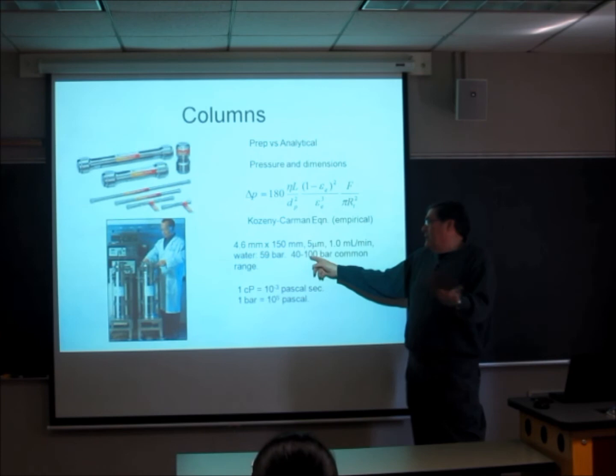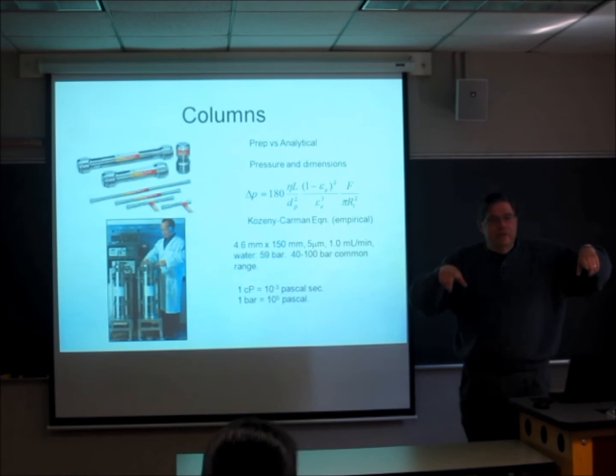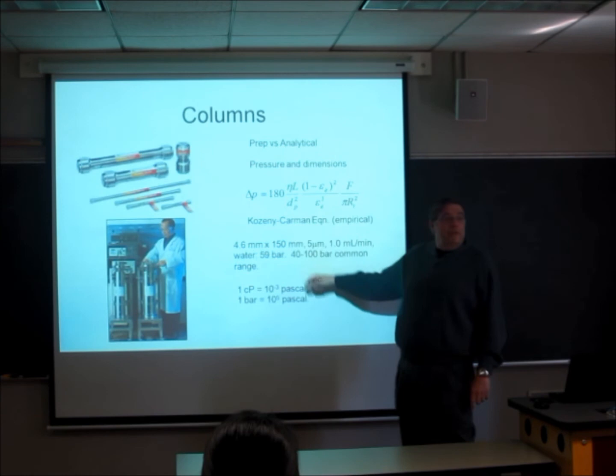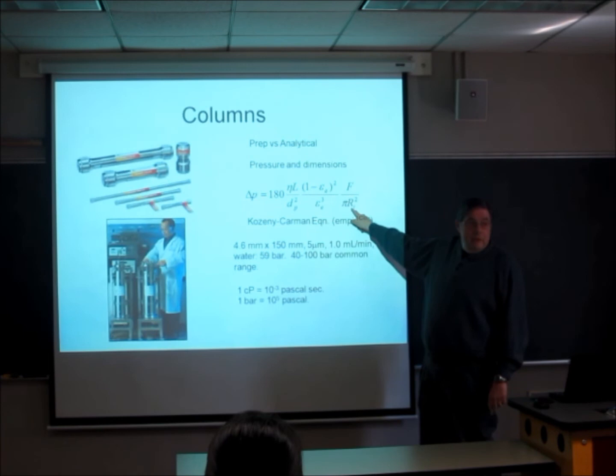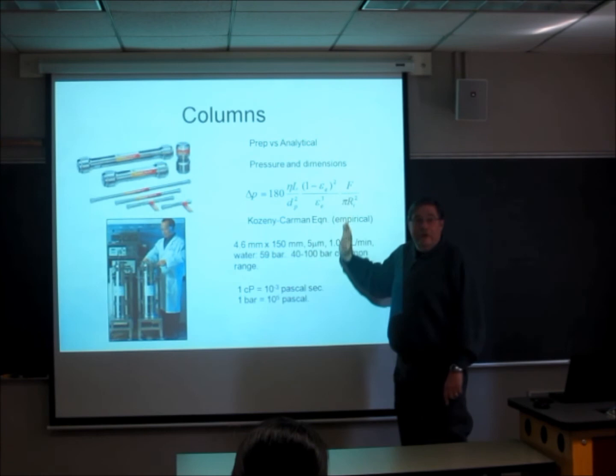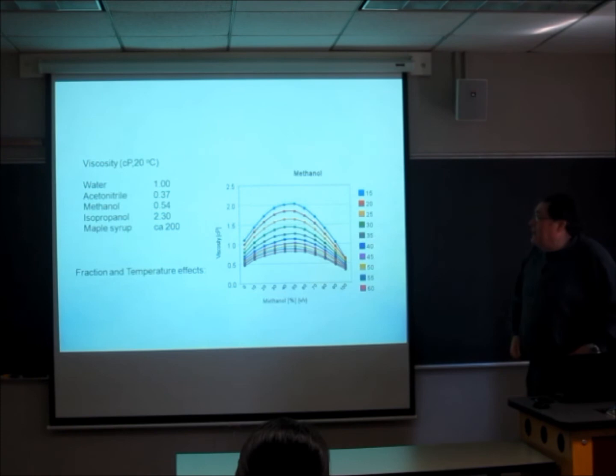There's been a lot of changes in particle diameter over the last 20 years or so. Five micrometers is pretty much standard for a lot of industrial applications, analytical quality control. But people are working at the edges now down below one micrometer. So if we go from five micrometers down to one micrometer, that's a factor of five. That increases the pressure by a factor of 25. That's a big change. So we go from, let's say, with a solvent combination, 100 bars to 2,500 bars. There are very few packings that can withstand that.